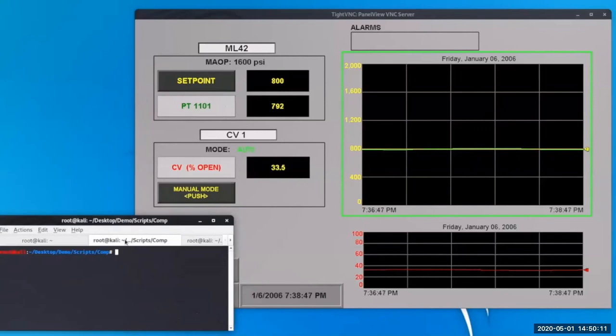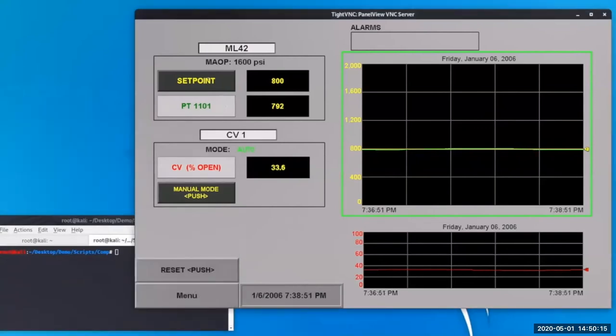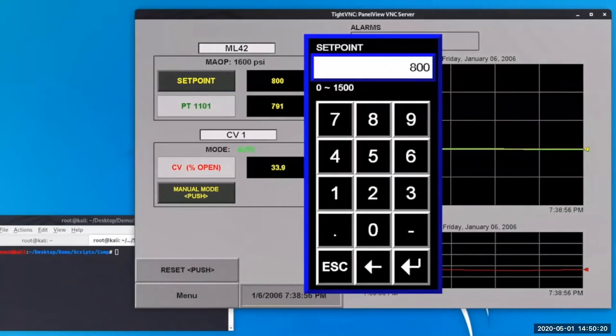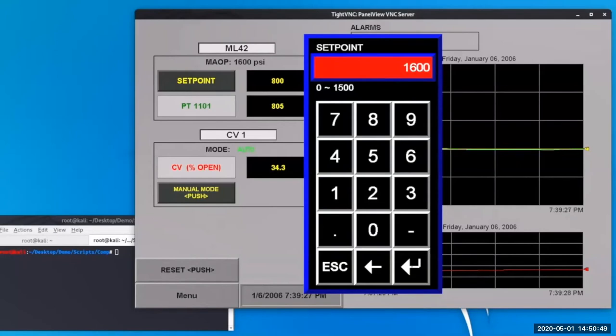To begin with the first attack, let's understand normal operation. An operator opens the set point window and selects a desired value. It's currently set for 800. Notice that the allowable range is 0 to 1500, which is well below the 1600 PSI maximum. If we try to add a value of 1600, we are denied — it's a hard set value in the HMI software developed by the engineer to prevent operations from accidentally going beyond the preferred amount.